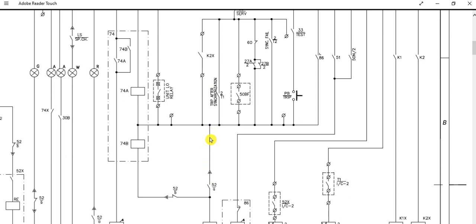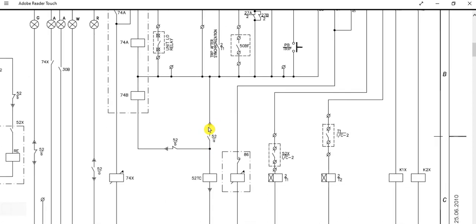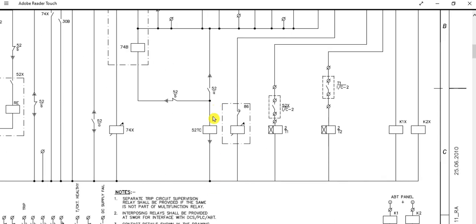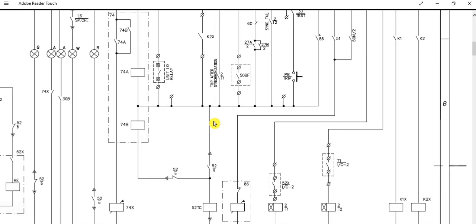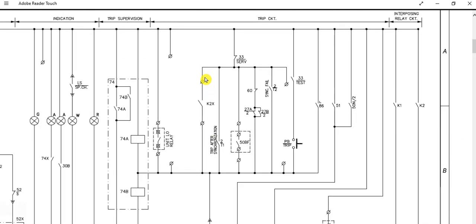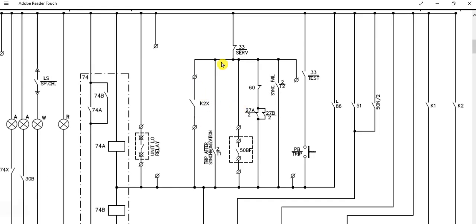The circuit breaker is presently closed and we want to trip it. 52a is an NO contact — when the breaker is closed, this is NC. So the path is through this, and it will energize the trip coil of the circuit breaker. In that case, the circuit breaker will be tripped. This completes the circuit and the breaker will be tripped. This is option one.